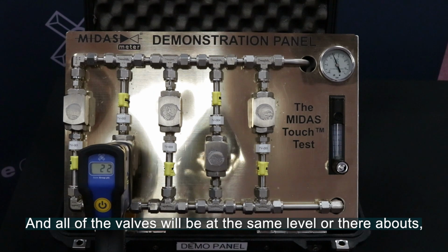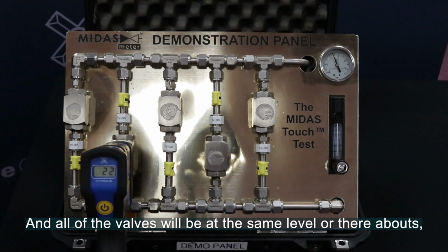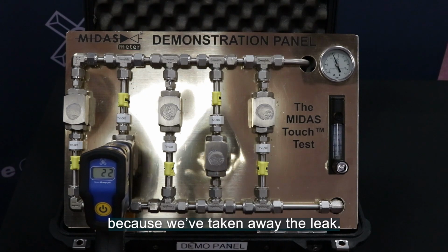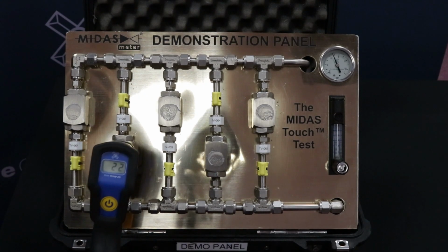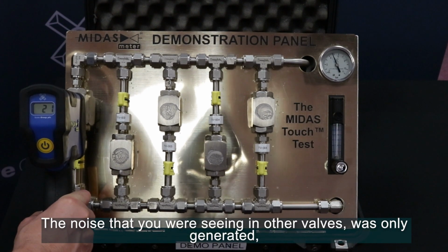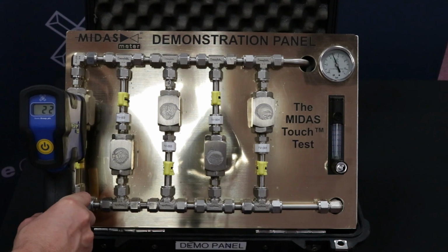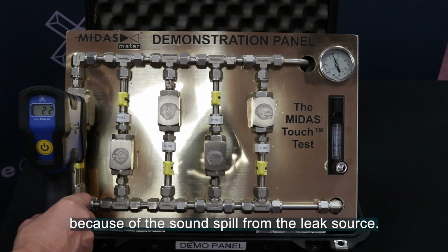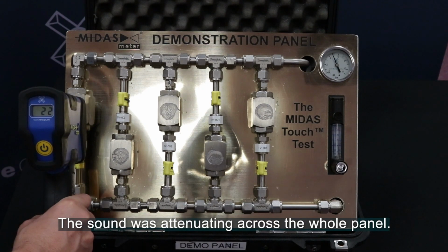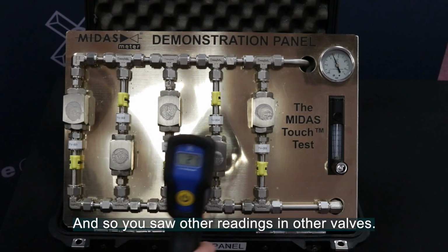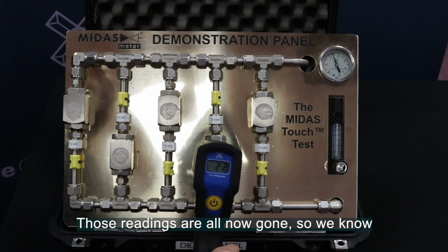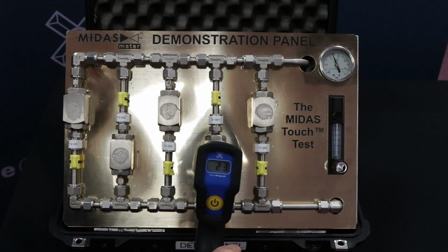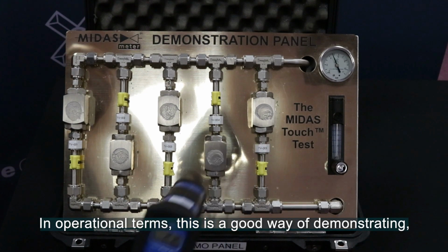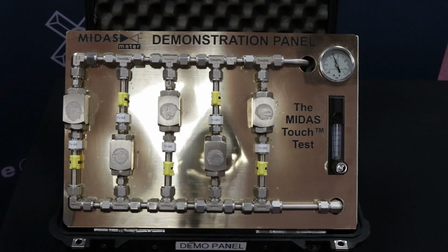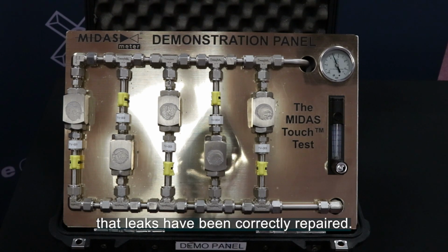And all of the valves will be at the same level or thereabouts because we've taken away the leak. The noise that you were seeing in the other valves was only generated because it was sound spill from the leak source. In other words, the sound was attenuating across the whole panel, and so you saw other readings in other valves. Those readings are all now gone, and so we know that we've repaired the leak satisfactorily. In operational terms, this is a good way of demonstrating that leaks have been correctly repaired.